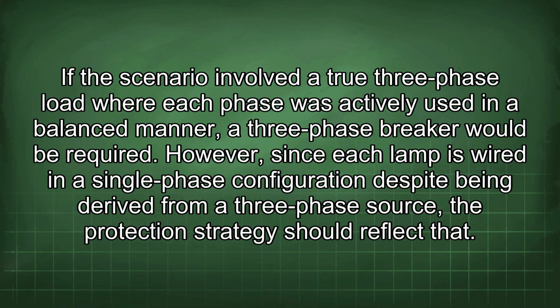If the scenario involved a true 3-phase load where each phase was actively used in a balanced manner, a 3-phase breaker would be required. However, since each lamp is wired in a single-phase configuration despite being derived from a 3-phase source, the protection strategy should reflect that.